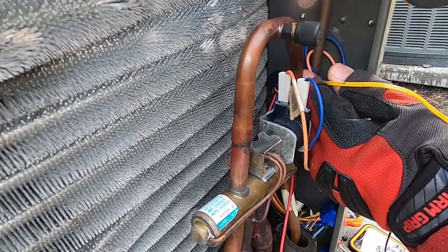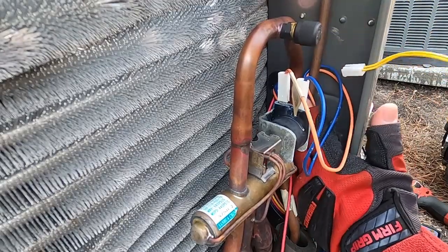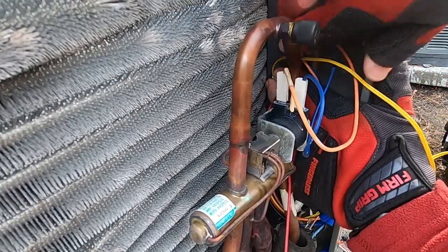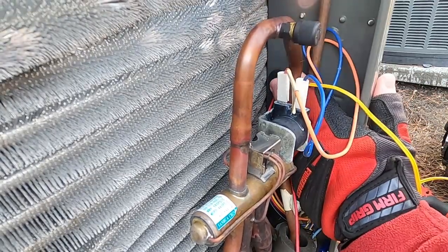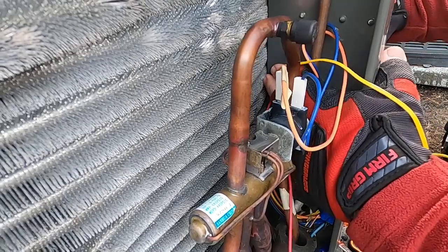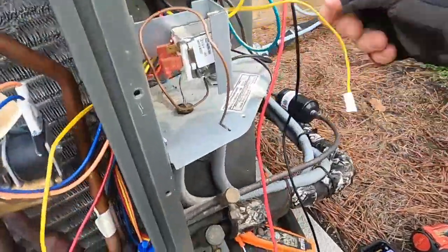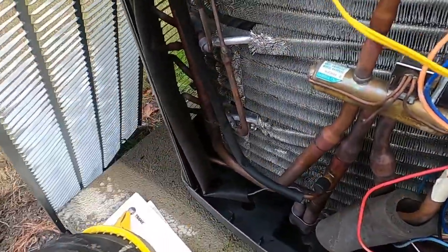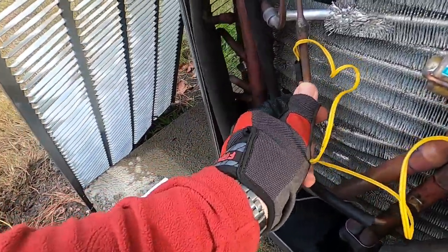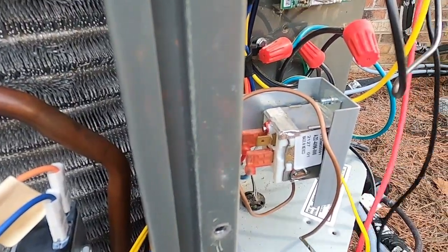If they had put this hole to feed these wires through about 3 inches higher and not right behind these two refrigerant lines where you're trying to get your fat fingers like I have, trying to feed them through there. Get in there. That through there, and then I'm gonna snap this sensor on there first, just let it sit for a minute, then I'm gonna check it, see if it's reading correctly. Should be. Brand new sensor.